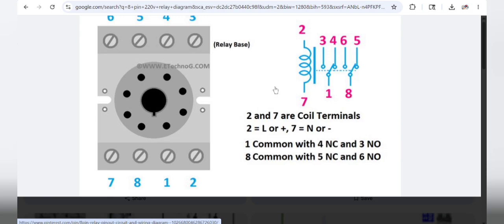Understand? So how to install the remote start signal to this controller? You need to install the AC relay, because you need to operate this relay with your main. When main is available, your generator should not start. When main is not available, your generator should start and shift the generator load to your load. Understand? So this is the basic concept. And how to install? This is the normally closed contact, normally meaning when the relay is not energized. When your 220 or 110 volt is not fed to this relay coil, this will be in a normally closed state.